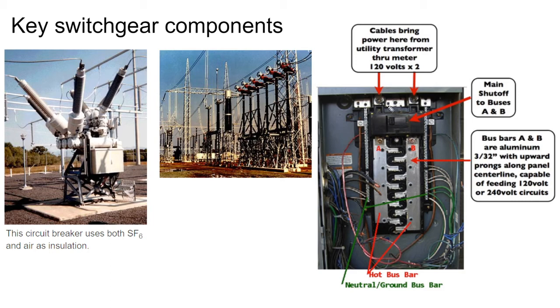When we talk about split phase power service, what we see here are bus bars that are alternating little ledges, and the breakers will snap on to these ledges and form a service panel. A double pole breaker will actually take up twice as much space as a single pole breaker and span two of these little teeth.